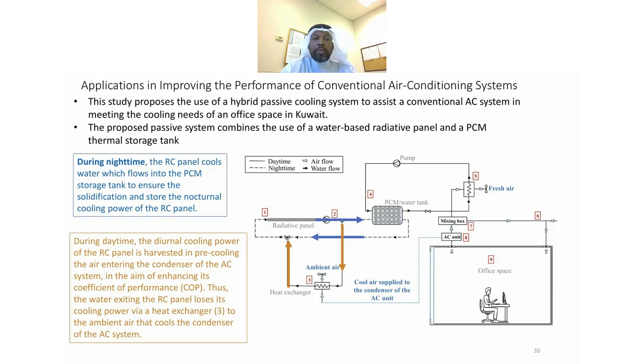The two other cycles are used during the day, shown by the orange lines. During the day, the diurnal cooling power of the radiative cooling panel is harvested to pre-cool the air entering the air conditioning unit through heat exchanger 3. The water leaving the radiative panel moves in this small cycle, exchanging heat with the ambient air at heat exchanger 3, before being directed to the condenser of the AC unit.